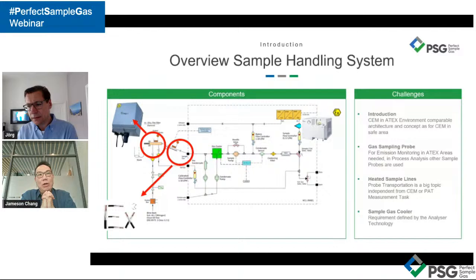At the end of the day, whether it is a pipe or the probe, the first thing is that we emphasize a few factors. First, it has to be above the water dew point, whether it is heated or non-heated. Then, because of different gases in the flue gas, next we have to address the acid dew point. Different gases have different acid dew points. Therefore, the probe that we are offering is above the water dew point and above the acid dew point, so that the sample always remains representative, without losses, as it is transferred from the sampling point all the way to the gas analyzer.